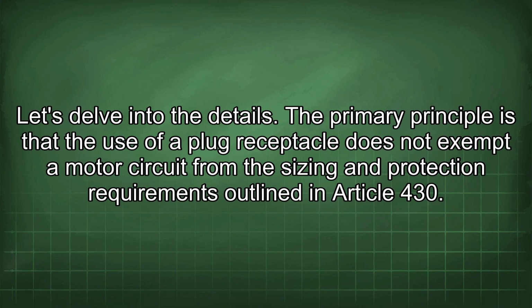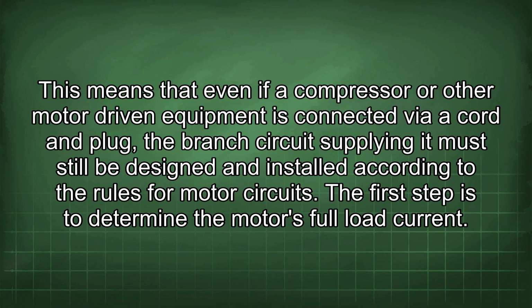Let's delve into the details. The primary principle is that the use of a plug receptacle does not exempt a motor circuit from the sizing and protection requirements outlined in Article 430. This means that even if a compressor or other motor-driven equipment is connected via a cord and plug, the branch circuit supplying it must still be designed and installed according to the rules for motor circuits.